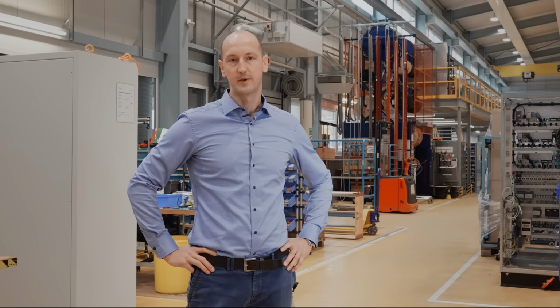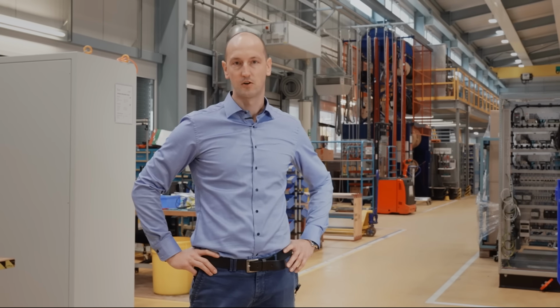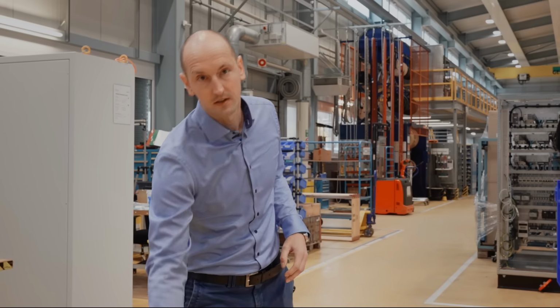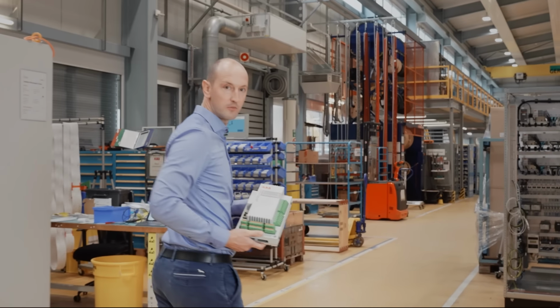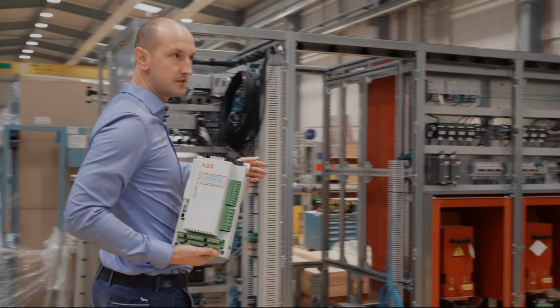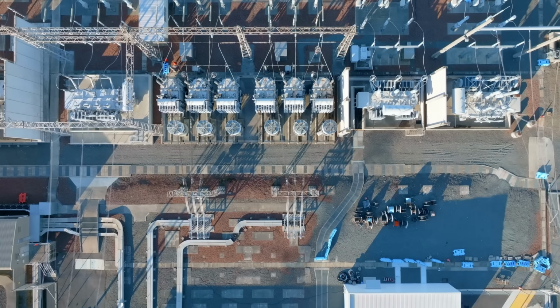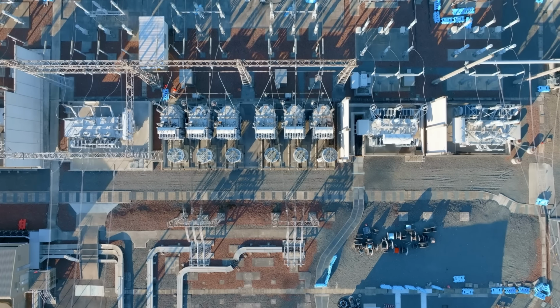An excitation system is important for synchronous machines like generators and motors. They provide the field current to the rotor winding, which is important for the magnetic field. We develop excitation systems for a wide range of power plants, from our smallest product, used in small hydropower plants, until the biggest units in the world, used in nuclear power plants. I think it's pretty important for the energy transition nowadays. We make sure that the power plants are on the grid, that they are stable, and that they're producing the right power when it's required.